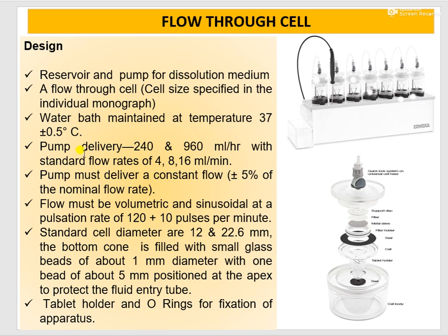Pump delivery will be 240 and 960 ml per hour with standard flow rate of either 4, 8 and 16 ml per minute. Means the dissolution medium will be pumped at 240 and 960 ml per hour at the flow rate, and you can choose the flow rate depending upon your requirement. It can be 4 ml per minute, 8 ml per minute and 16 ml per minute.